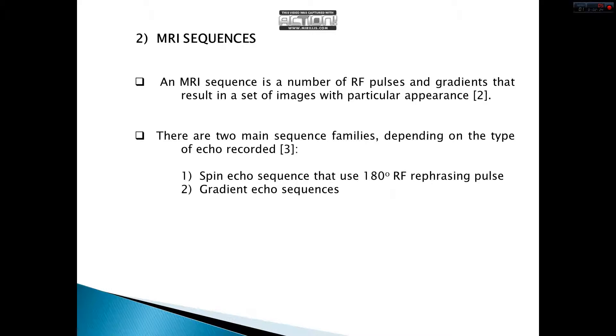This is called an MRI sequence. An MRI sequence is a number of RF pulses and gradients that results in a set of images with particular appearances. There are two main families of sequences with respect to the type of echo occurrence. One of them is the spin echo sequence, which uses 180-degree RF rephasing pulses, and the other is the gradient echo sequence. We will focus on the gradient echo sequence.